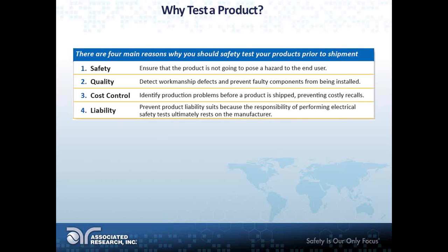For safety, we want to ensure the product isn't going to pose a hazard to the end user. That's why we run these tests, and that's why they're called safety standards. For example, IEC/UL 61010-1 3rd edition for laboratory equipment is a safety standard. It goes through all the different hazards a product could pose, how you mitigate those risks, and how you test to make sure it's compliant with those standards. There's a reason we have standards: to make sure everybody's on the same page with regards to testing and compliance, so that the products out on the marketplace are safe for use.